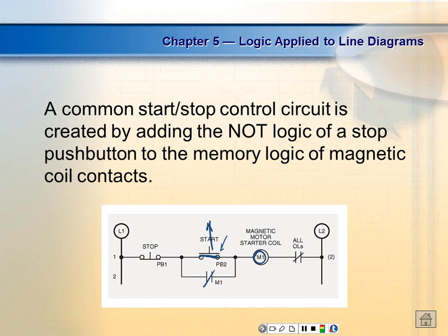It's called a seal-in circuit. It's called a 3-wire circuit. And how I got that name, I'm not really sure. But if you talk about a 3-wire control, they're talking about a circuit with a seal-in. Are we okay? Yes.